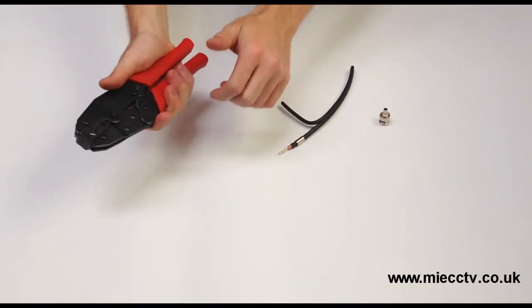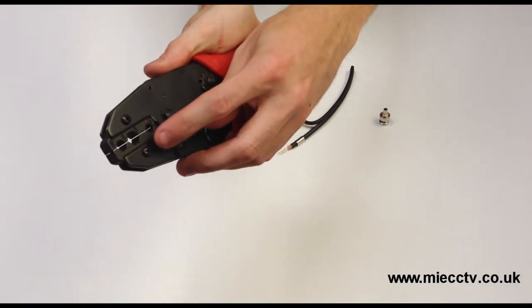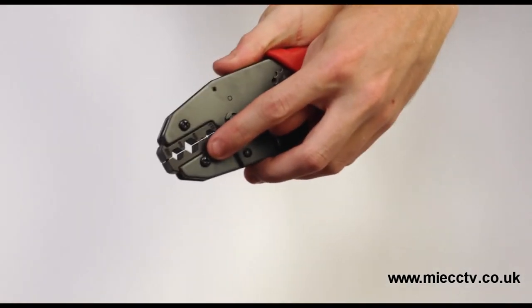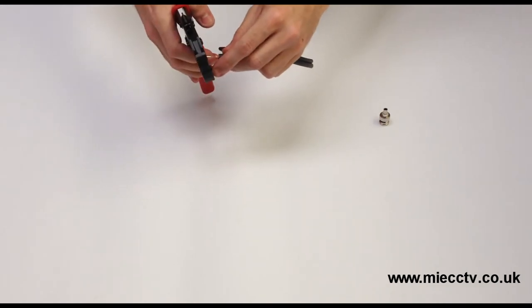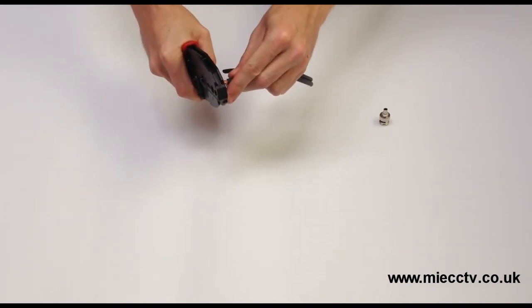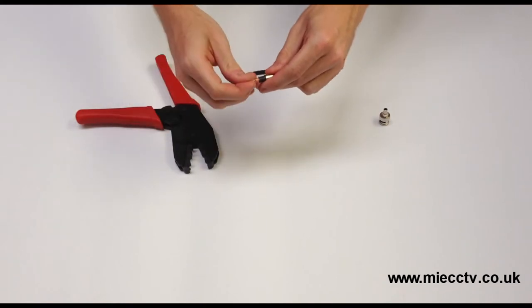Our BNC crimp connector requires a 0.068 inch crimp so please ensure your crimp tool has the appropriate cavity for crimping. Now place the pin into the cavity and crimp it down using the ratchet to ensure the pin is secured tightly.